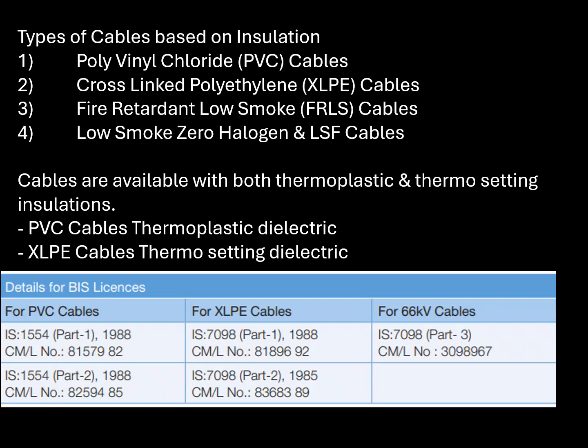Cables can be classified based on their insulation type. First and most used is polyvinyl chloride, PVC cable. Second, cross-linked polyethylene, XLP cables. Third is fire retardant low smoke, in short known as FRLS cables. Fourth, low smoke zero halogen, LSZH cable. Cables are available with both thermoplastic and thermosetting insulations in PVC and XLP.